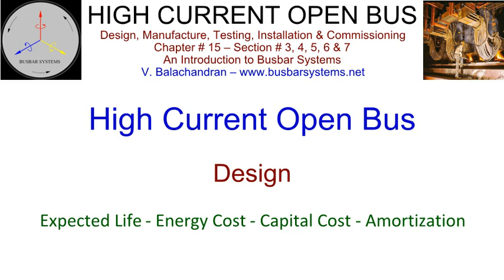Optimization can be carried out based on expected life, energy cost, capital cost, and amortization. In energy-intensive processes and plants, the contractor is expected to guarantee the energy required to produce a unit of product. A limitation is therefore imposed on the energy consumption of various components. Based on this limit and knowing the route length of the connection, the area of cross-section of the conductor can be arrived at. In most cases, the temperature rise limitation is never a design criterion.